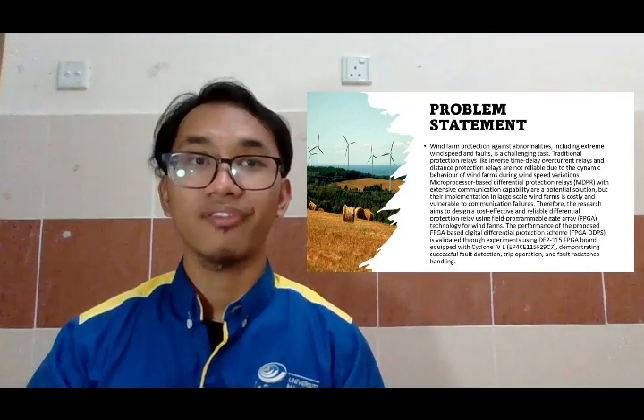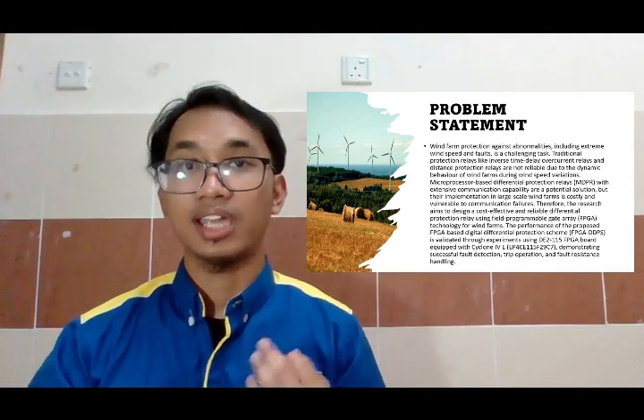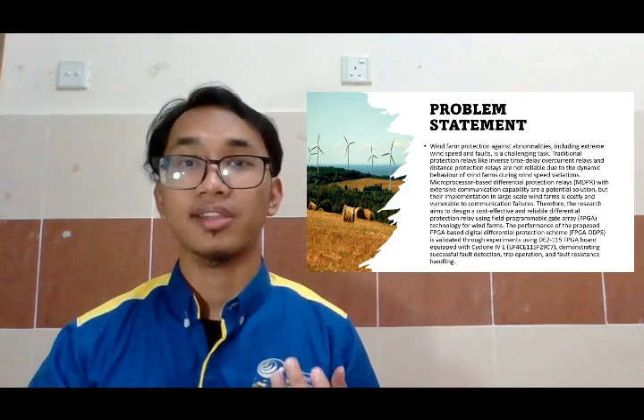For the problem statement, wind farm protection is a challenge due to extreme wind speed and faults. Traditional relays are unreliable due to wind farm dynamics. So, microprocessor-based relays with extensive communication are a potential solution but are costly and vulnerable to communication failures. This research aims to design a cost-effective and reliable differential protection relay using FPGA technology. Experimental validation of the FPGA DDPR demonstrates successful fault detection and trip operation.